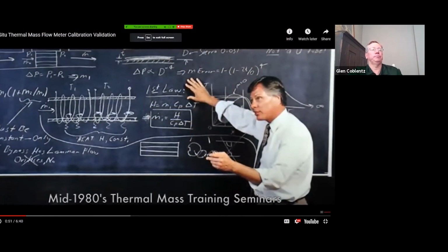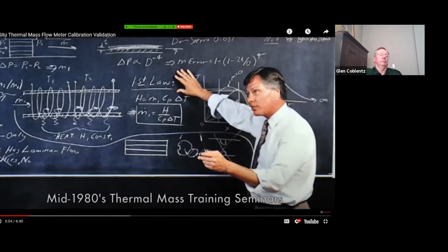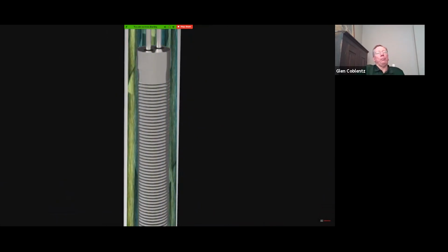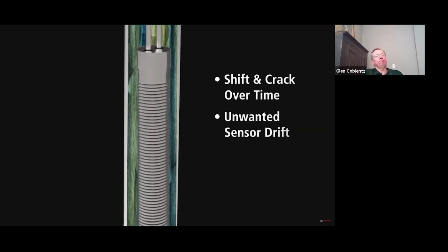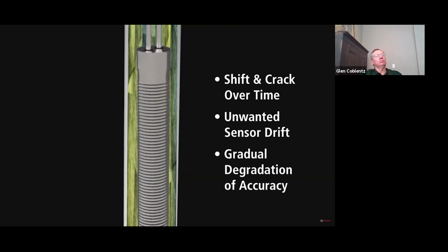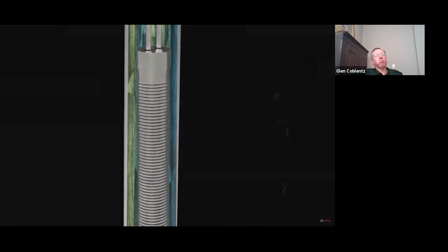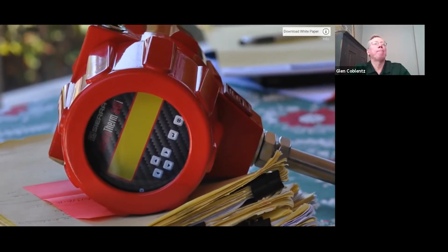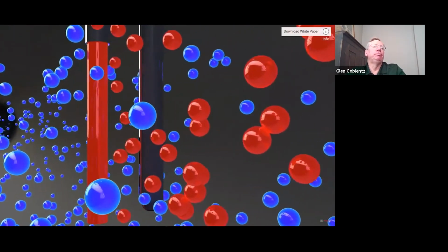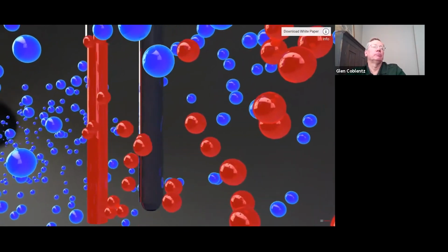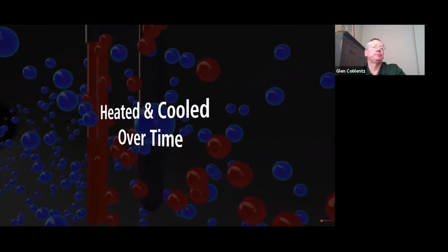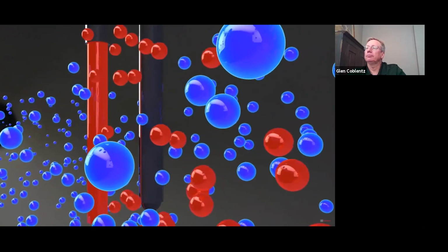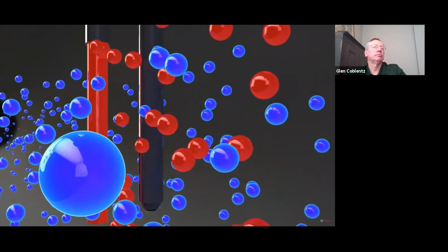Dr. Olin pioneered the innovation of an all-metal clad thermal sensor in the early 1980s. Wet thermal sensor design, because of the organic potting cement used, would shift and crack over time, causing unwanted sensor drift, resulting in a gradual degradation of flow measurement accuracy. Today, wet thermal sensors are used by all industrial thermal sensor manufacturers on the market, with one exception, and that is Sierra. Sierra never stopped improving the technology, knowing that wet sensor drift problems must be solved. After all, by its very principle of operation, a thermal sensor is heated and cooled over time, expanding and contracting the cement inside the sensor, making it crack, settle, and shift from its original state.